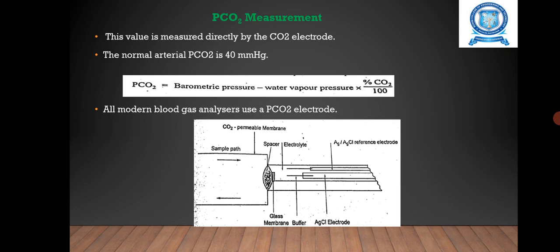Here we have two differences. The first difference is that in this electrode, the blood sample comes in contact with a CO2 permeable membrane such as teflon, silicon, or rubber. The next one is pH sensitivity glass, as in pH electrode.